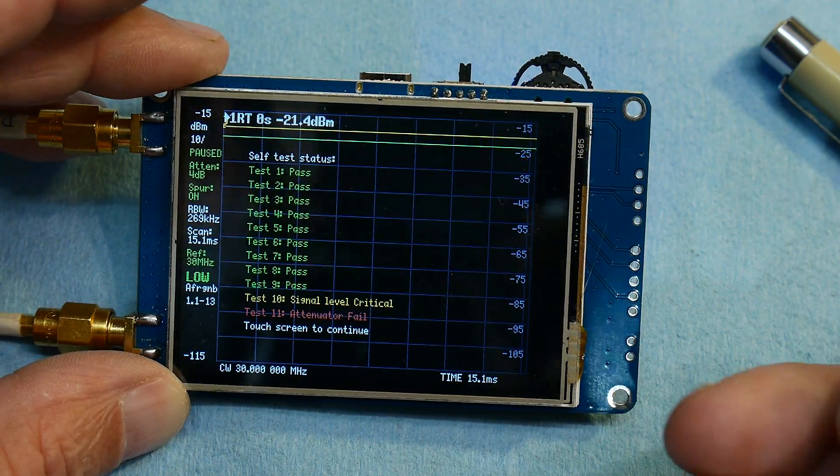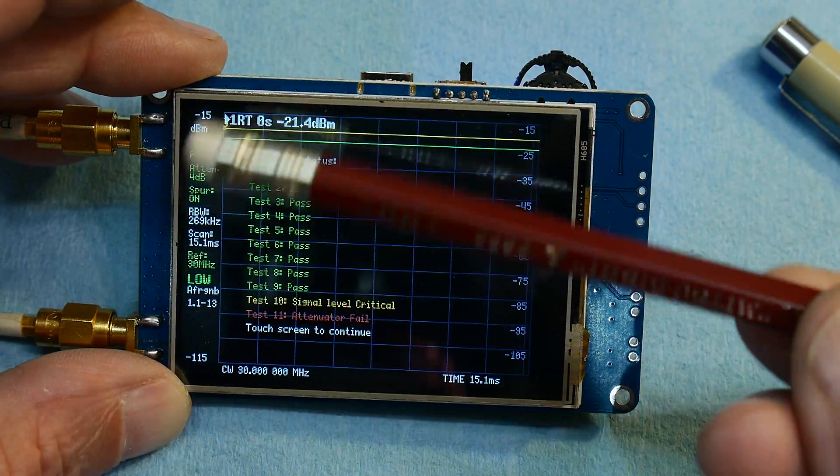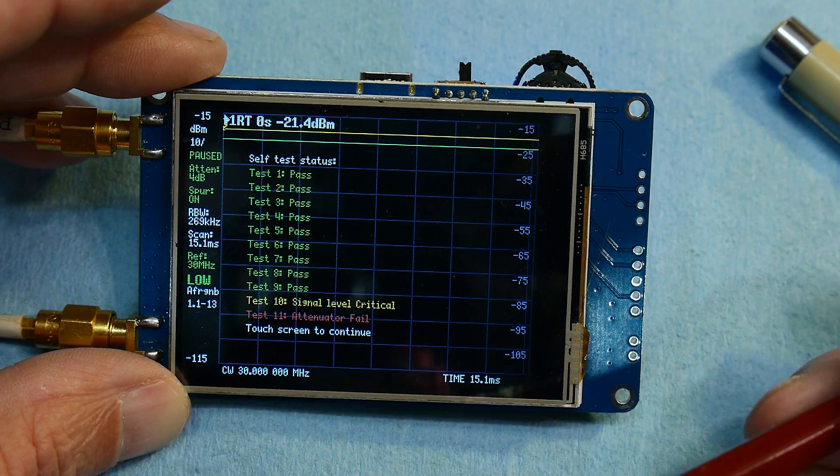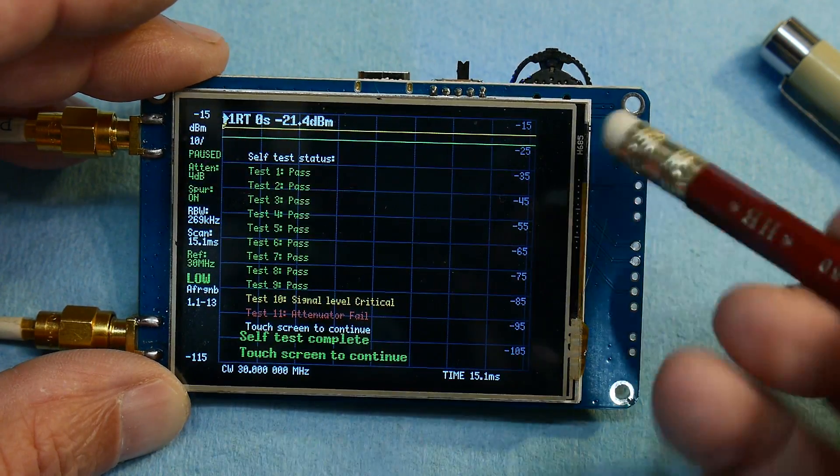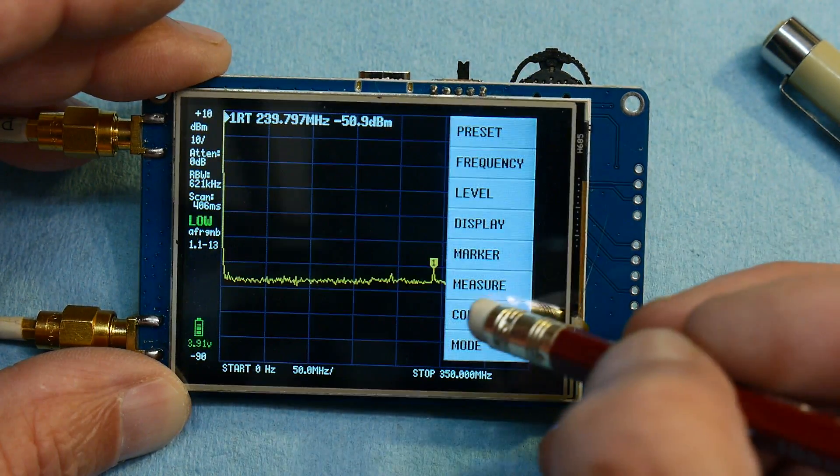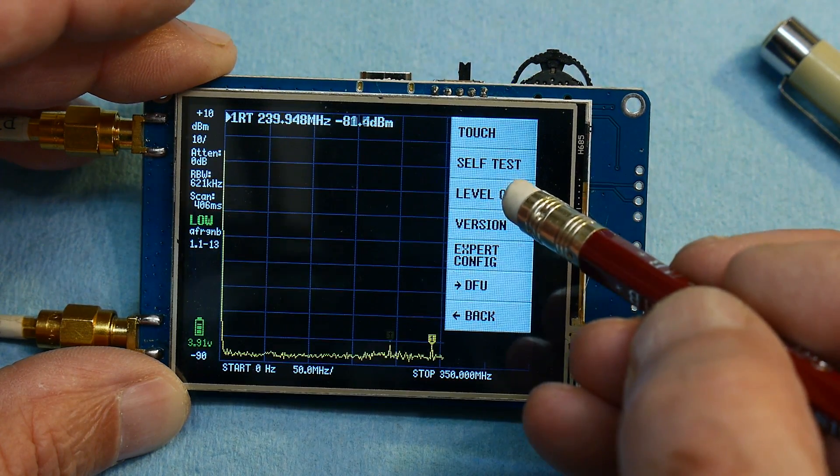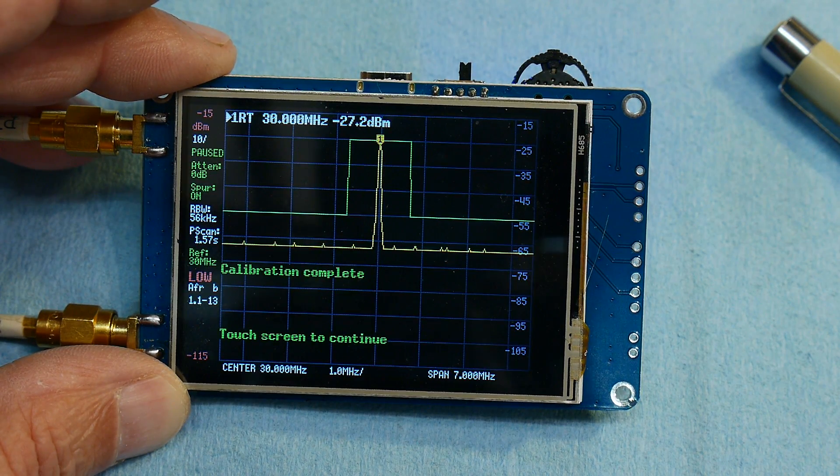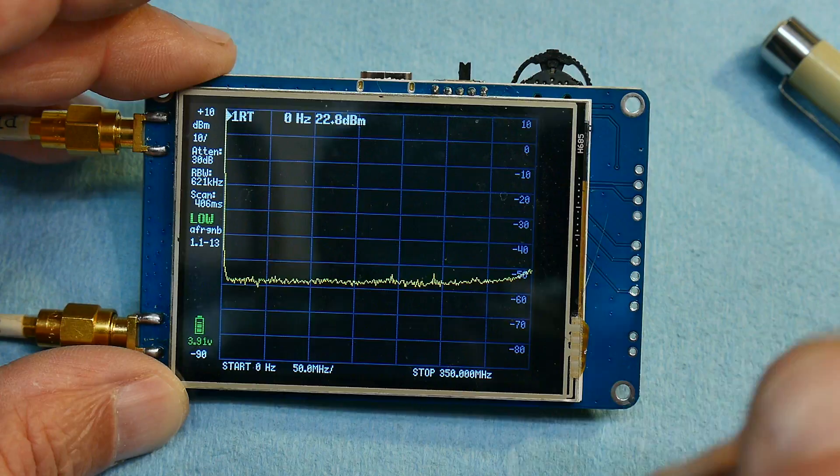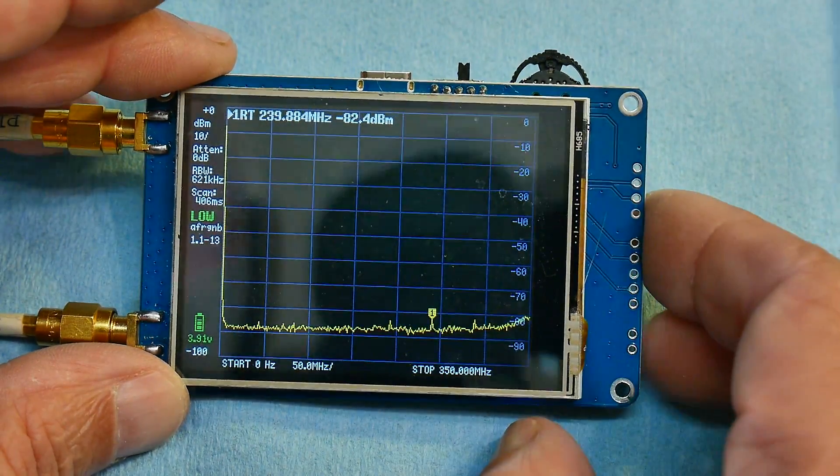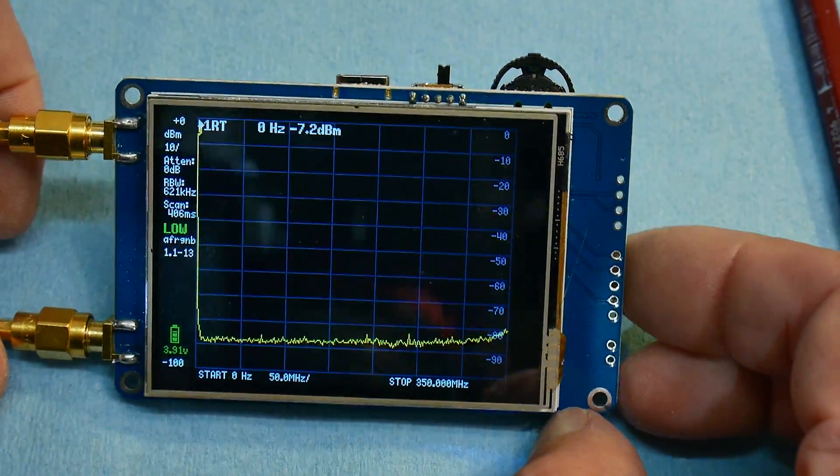And then it says test 11 attenuator fail. And it's attenuator 4 again. So I've tried a brand new part and still I get a 4 dB step problem in test 11. But now I have additional information that step 10 is funny too. If I do a level cal, everything's just fine. So something else is sick with the TinySA.